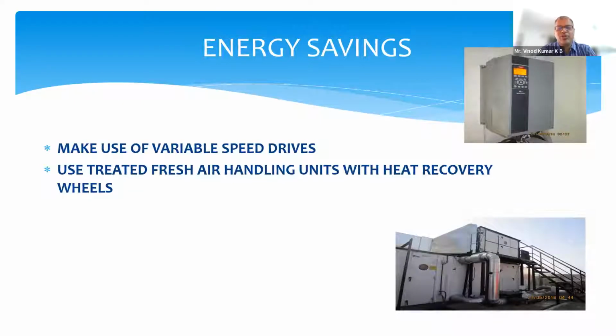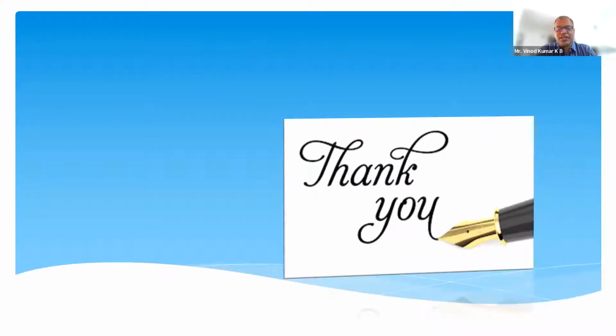Okay, so I come to the end of this section on air handlers: construction, how to operate, how to maintain them, and how to take care of your selection so that you do not have maintenance, tripping or breakdown issues with the AHUs. One theater can have only one AHU. No system says that you should have a standby AHU. That's how the design is going to be. So select them right, so that you don't have a problem.